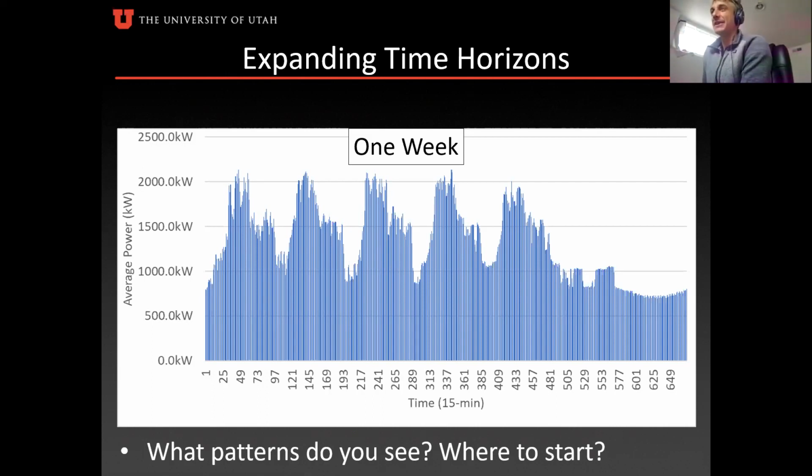That's great. Yeah, just by what you said, just by looking at these patterns, you can start to maybe not get full conclusions, but get some ideas about what's happening at these facilities without knowing anything about the process. And these weekday peaks even have two separate things happening, like Michael said. So you really want to know what's being turned on at those times. It helps you come up with some targeted questions for these facilities before you go there.